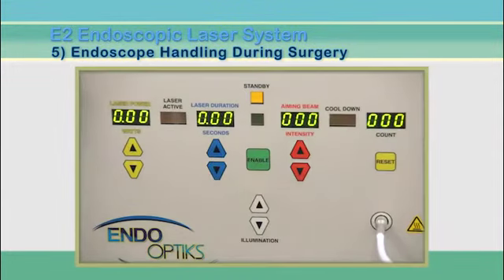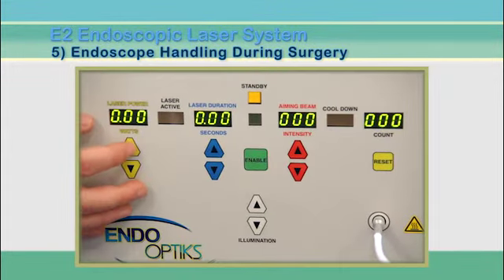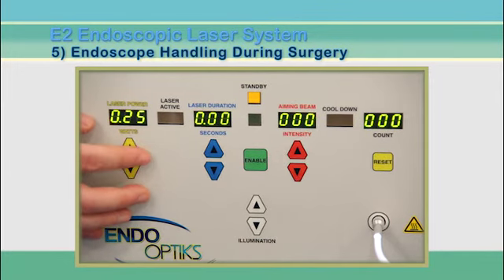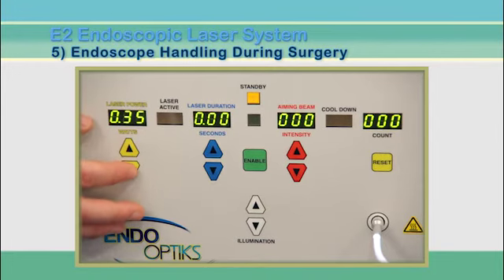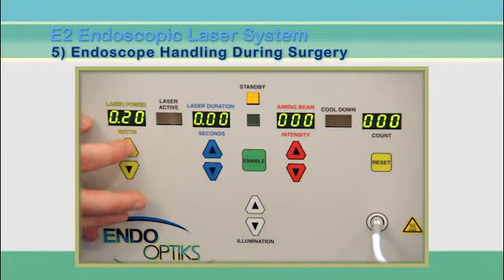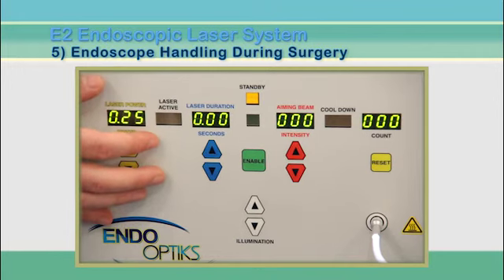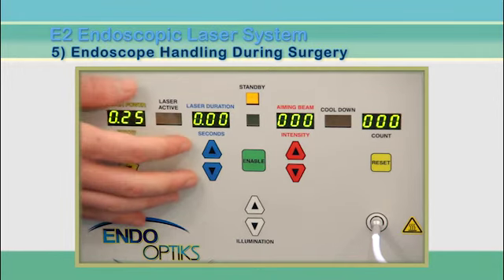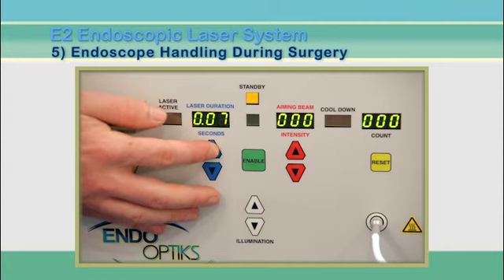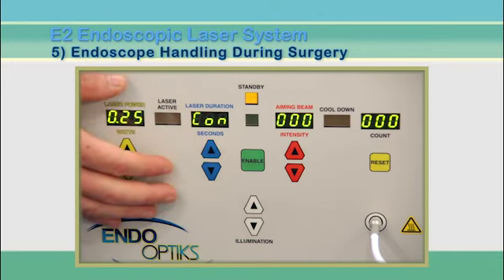The next step is to set the laser parameters. Beginning on the left of the panel and moving to the right, set the laser power to 0.25 watts on the power display by pressing the up arrow. This may be raised or lowered during surgery at the direction of the surgeon. The next control is for laser duration. Depress the up arrow until the display reads CON. This means that continuous laser power is delivered as long as the pedal is depressed.